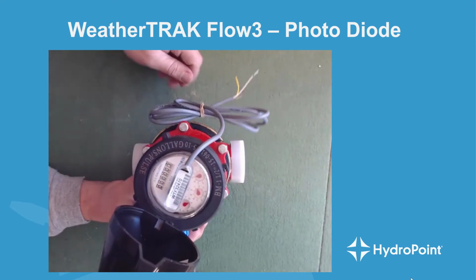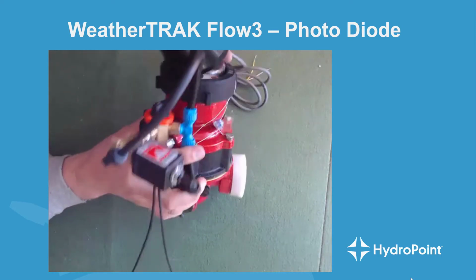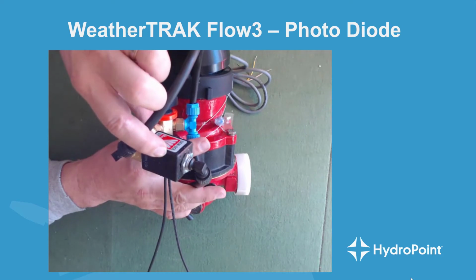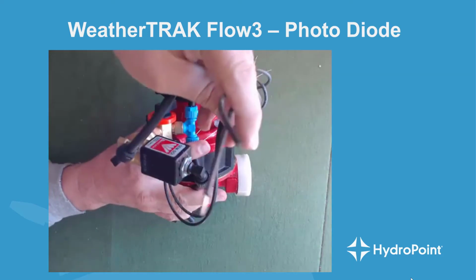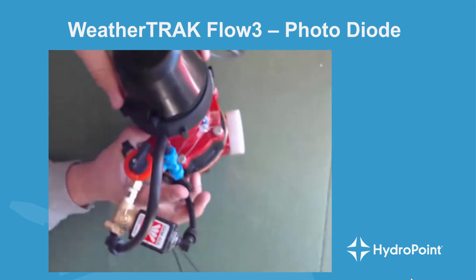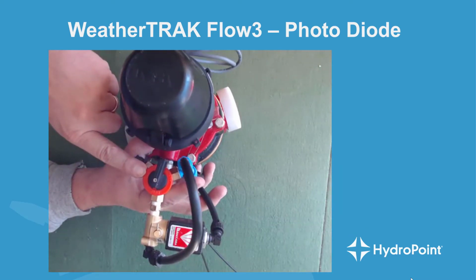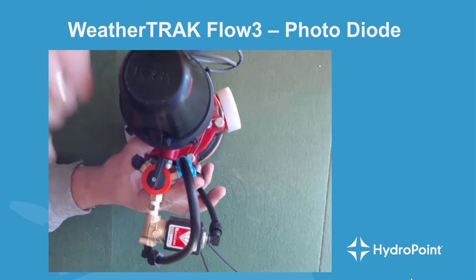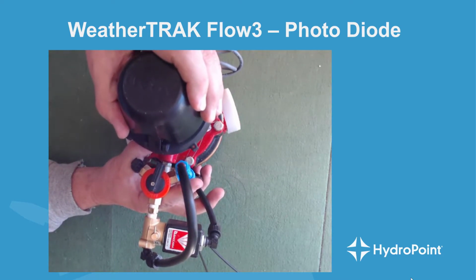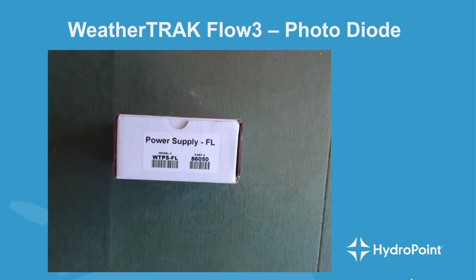Then the black box on the side of the Flow 3 is the master valve solenoid. On the side of the sensor, you'll see that it has the two valve wires coming from the solenoid. And then other things to pay attention to are the three-way selector switch, as well as the solenoid bypass selector switch right here at the base of the solenoid.